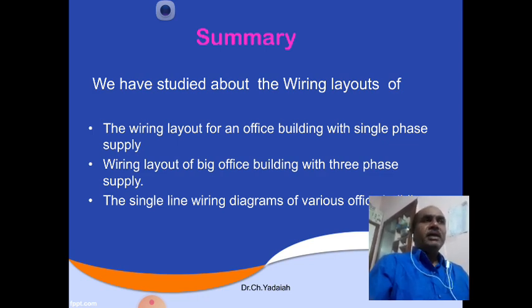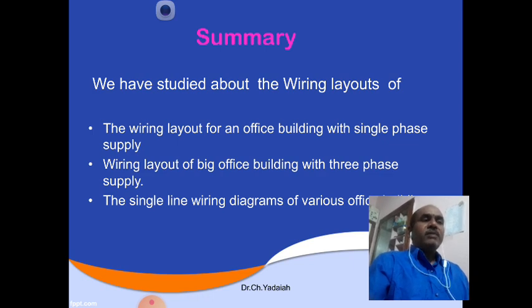After that, find the length of the conduit, then multiply by 3 to get the length of the wire for single phase, and find out the number of PVC accessories and switches, all things, and you tabulate all of it, it becomes a schedule. After getting the schedule, we estimate the approximate labor cost, then give the overall idea of the items and cost with some approximate value. This is the total estimation and installation cost of a domestic wiring.